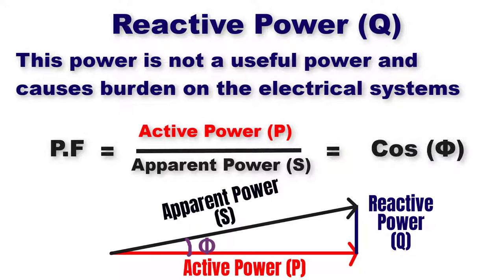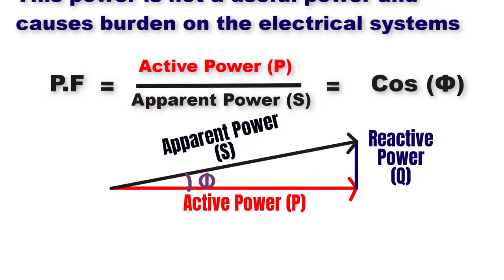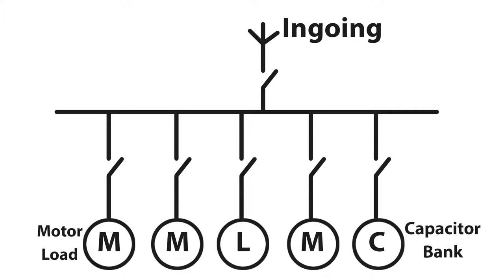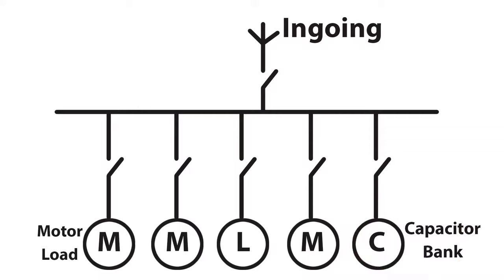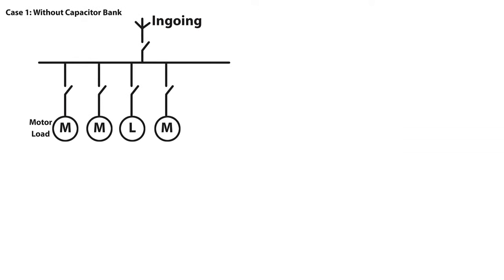In practical life, if we have a substation with loads like motors and lighting, we connect in parallel to the bus bar a capacitor bank that will improve the power factor. As you can observe in this figure, we have active power P in kilowatts and reactive power Q — caused by inductive elements on the motors — in kilo volt ampere reactive.